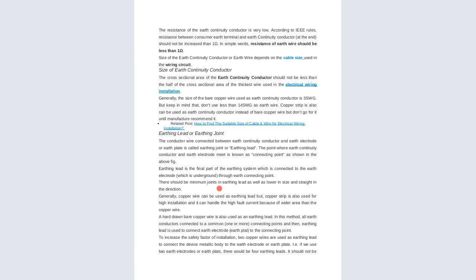There should be a minimum of joints in the earthing lead, and it should be low in size and straight in direction. Generally, copper wire can be used as the earthing lead, but a copper strip is also used for high installation, and it can handle a high fault current because of its wider area than the copper wire. A hard drawn bare copper wire is also used as an earthing lead. In this method, all earth conductors are connected to one or more common connecting points, and then the earthing lead is used to connect the earth electrodes, that is the earth plate, to the connecting point. To increase the safety factor of installation, 2 copper wires are used as the earthing lead.